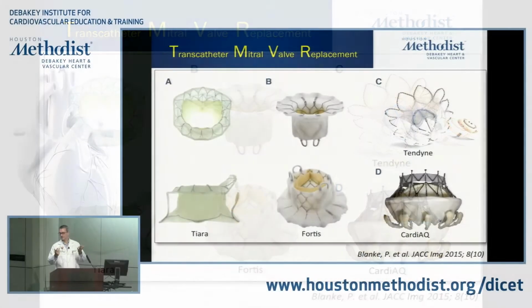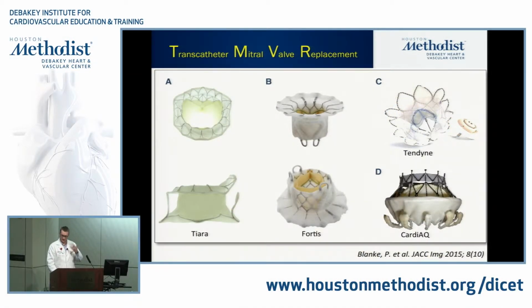The challenge with all these devices, if you think about the hemodynamics, is that these devices have to hold back LV systolic pressure, 140. TAVR devices have to hold back aortic diastolic pressure, which is 70. So it's at least, on an average, double the pressure gradient that these devices have to hold back. They're larger, so they act like sails, covering a bigger area. So engineering-wise, it's harder. It's a bigger device. It's subject to more surface area for pressure. It's at least twice the systolic pressure.